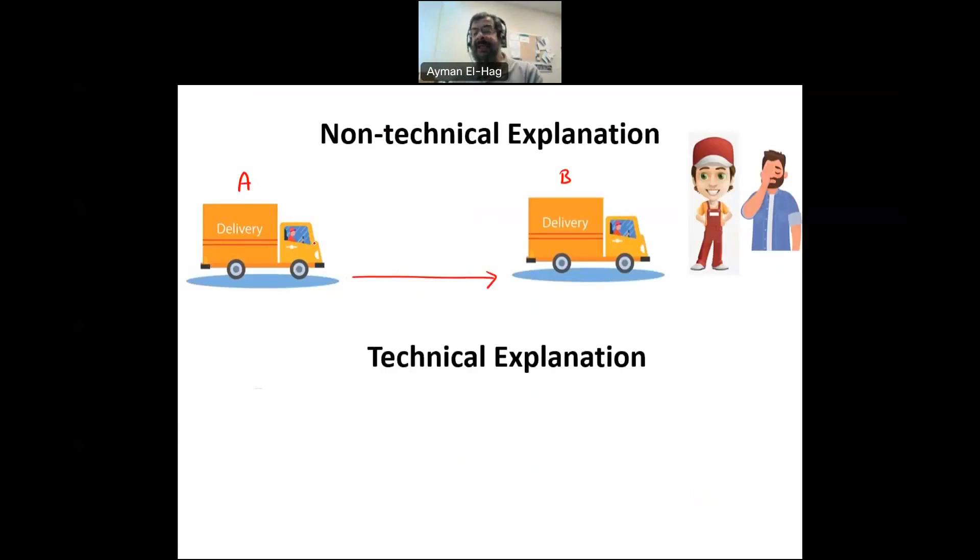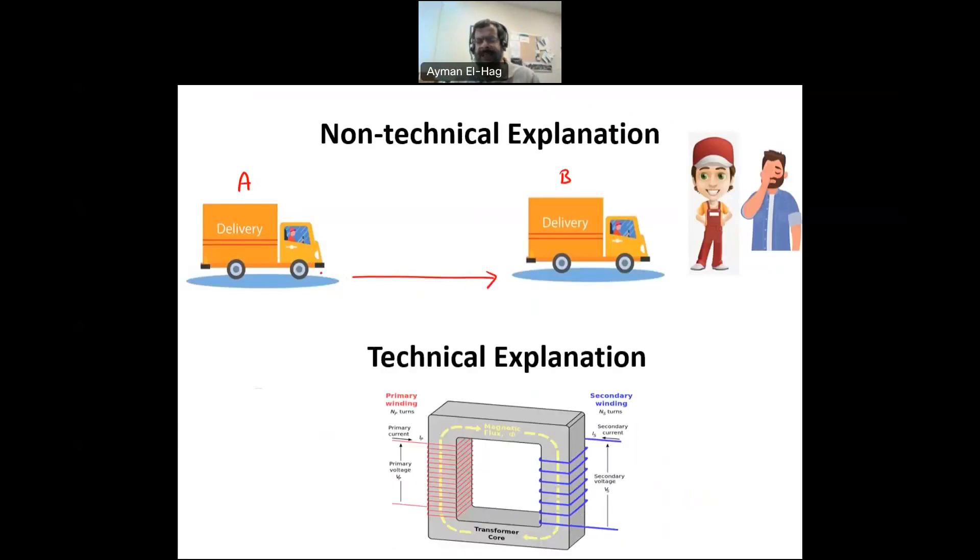And if I give a technical example, the same transformer example, imagine that the secondary side of the transformer is an open circuit. There is no load. So you energize the transformer. It's the same amount of flux there in the core, but you are not delivering any power. So here the reactive power is considered as a loss, as useless amount of power because you are not delivering power from point A to point B.